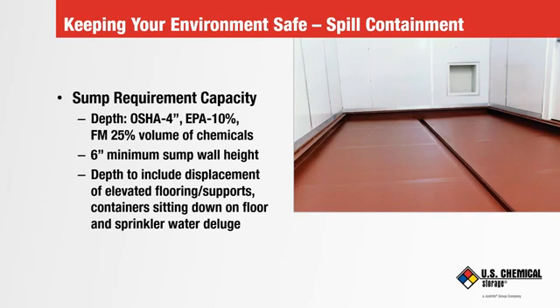But it lacks details. For example, to find out how low a ceiling can be, it's not in NFPA 30. You have to refer to OSHA Title 29, paragraph 1910.37I. It says the distance must be 7 foot 6 inches from the chemical storage building's elevated flooring to the finished ceiling. Even though NFPA 30 agreed with the EPA, FM, on their own, raised the sump capacity from 10% to 25% of what's stored. For storage of common 55-gallon drums sitting on an elevated floor, this results in the sump wall having a minimum height of 6 inches. You can begin to see why knowing what's in what codes is very important.